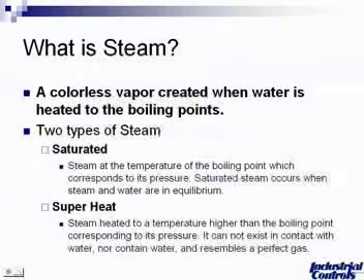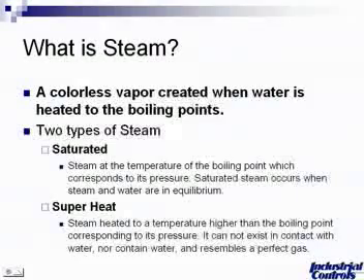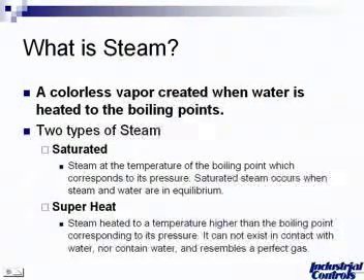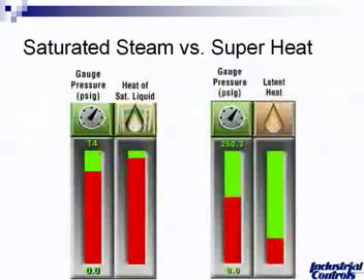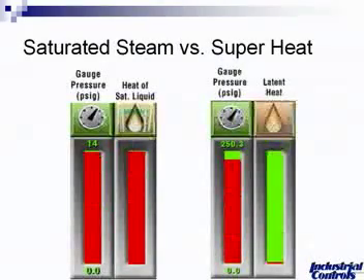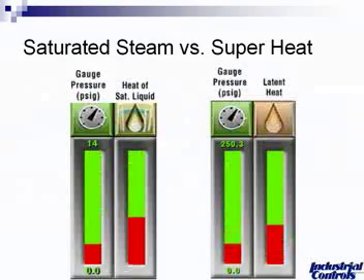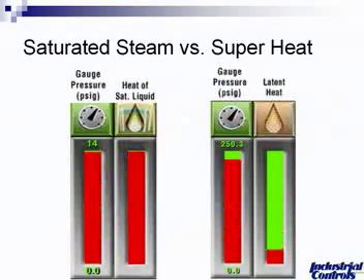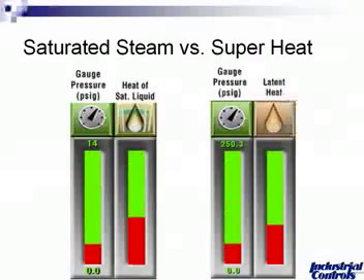Superheated steam you'll find more in the power industry. Superheated steam is steam heated to a temperature higher than the boiling point corresponding to its pressure. It cannot exist in contact with water nor contain water and resembles a perfect gas. This slide shows a saturated steam condition where we're discussing gauge pressures. As gauge pressure increases, heat or temperature increases; as gauge pressure decreases, you'll see our latent heat or BTU transfer increases.